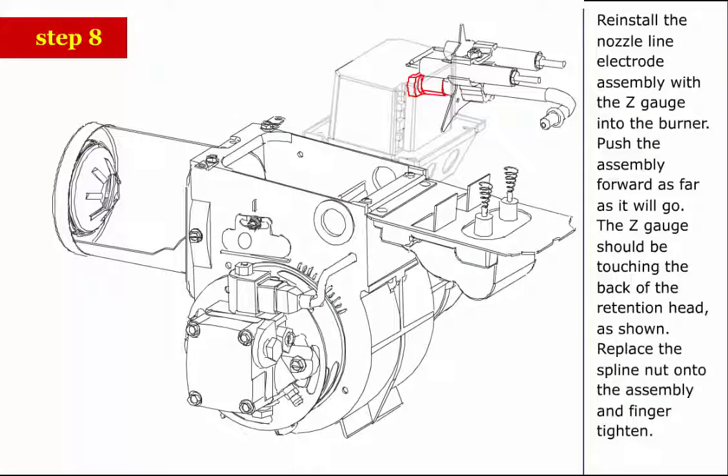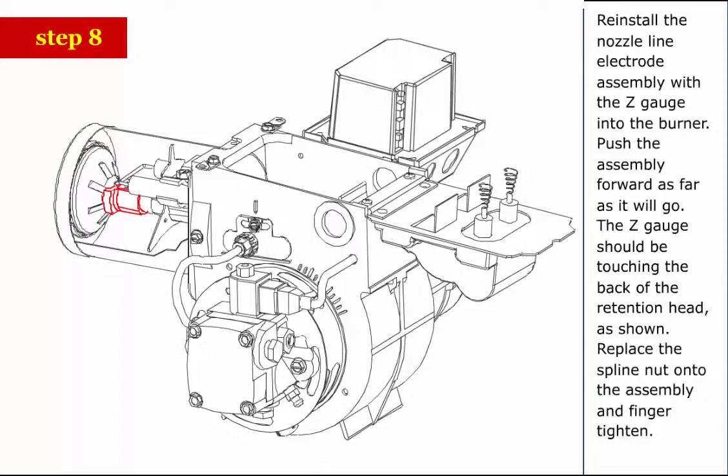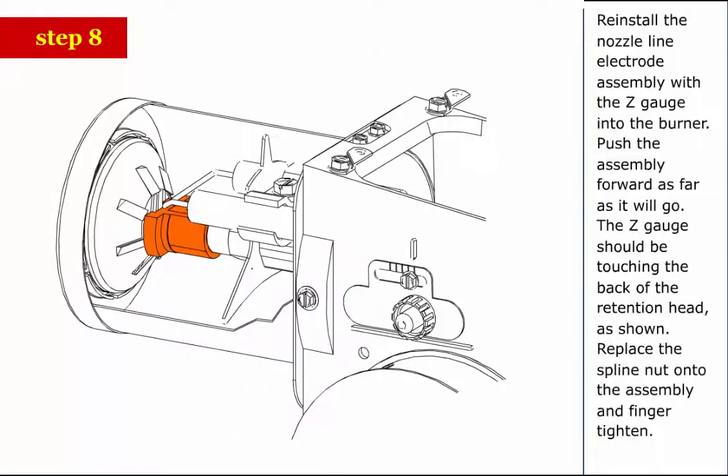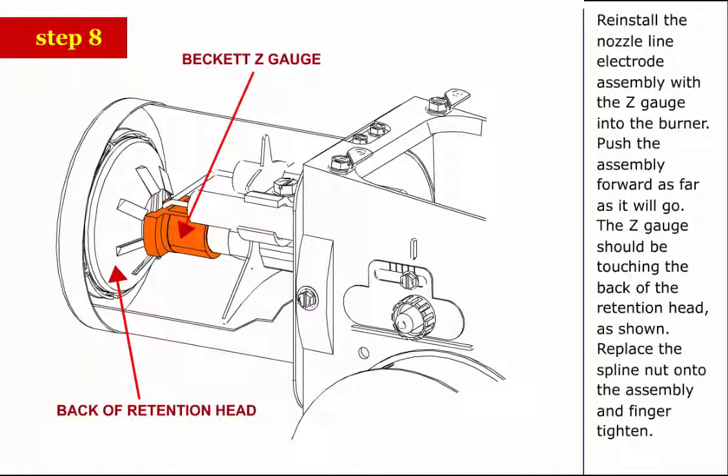Step 8: Reinstall the nozzle line electrode assembly with the Z gauge into the burner. Push the assembly forward as far as it will go. The Z gauge should be touching the back of the retention head as shown. Replace the spline nut onto the assembly and finger tighten.